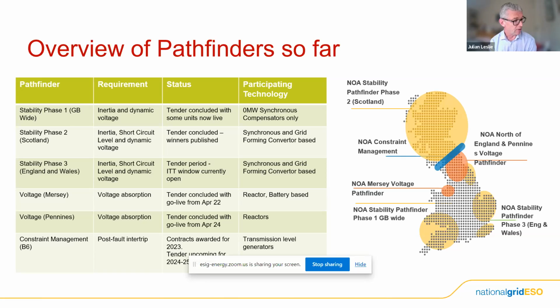To give a sense of scale, stability phase two was about £330 million over a 10-year period. So £30 million a year for 10 devices, which are providing short circuit infeed. That's providing us system security and making sure the system is stable. It's allowing us greater integration of renewables and inverter-based resources. But more importantly, it's avoiding us having to run gas-fired power stations within Scotland to maintain grid system stability. So that £30 million a year is saving the consumers tens of millions of pounds a year, if not hundreds. And we expect the benefits from phase three, because this is really tackling exactly what the gas power plants are delivering to us in terms of short circuit and voltage control in those regions, to be even greater.